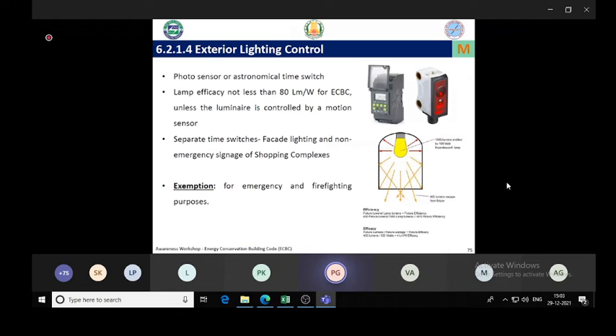Right. Now, in exterior lighting control, we have a mandatory requirement of either a time switch or a photo sensor to control the exterior lighting, street lighting and facade lighting. And the lamps used in the street lighting should have an efficiency of 80 lumens per watt. So basically any LED should normally meet this requirement.